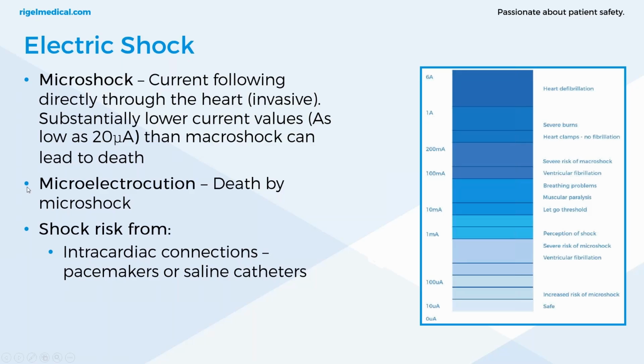Death by microshock is known as microelectrocution, and there's been several studies that have recognized the physiological effects of electrical current, and this is both for macroshock and microshock. These studies have been performed, and what you'll find is that international standards, NFPA 99, will always reflect those conditions and those effects, which is why you'll see that patient leakages have much lower test limit levels than those of equipment leakage test limits.